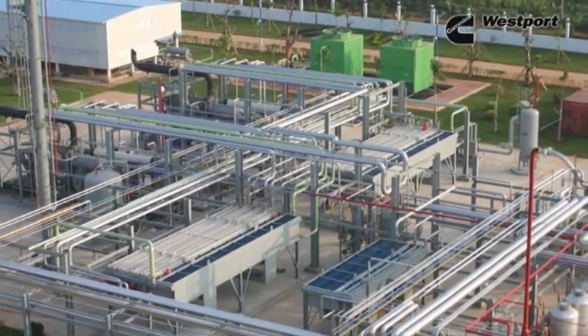LNG is typically produced in a liquefaction plant and delivered via truck to refueling stations, where it's stored in tanks. So it can be offered in locations where a natural gas pipeline isn't available. Refueling time is similar to diesel or gasoline fuel. The LNG fuel tank is designed to be top-filled through a single fill hose with no vent return. This is accomplished by spraying subcooled LNG into the vapor space of the tank—the cold liquid condenses the vapor and creates space for itself inside the tank, eliminating the need to vent product.